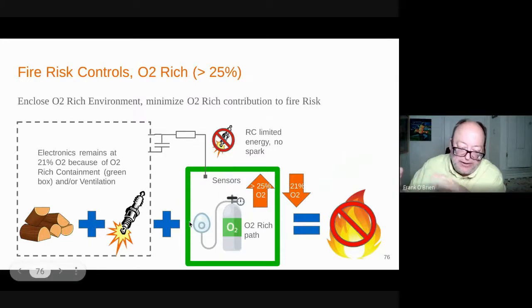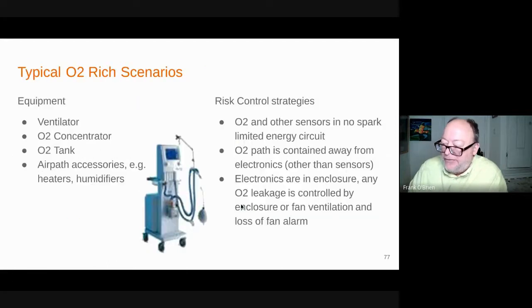Now, if we're making ventilators, etc., we need to monitor that oxygen. Generally, we want to measure it and know its concentration. So there's at least a sensor in there. And so the sensor needs to make sure it's in an energy limited circuit. And so that is something we try to do. So we keep everything away from the oxygen rich breathing path, except the sensor, and then the sensor complies with that safe limit stuff, and then everything else is away from more than 25%, so it's the normal requirements we already talked about. And so typically, with ventilators, oxygen concentrators, oxygen tank, and their breathing paths, accessories, this is all very relevant. And we would take those approaches. We know the sensors are in there, but everything else won't be.